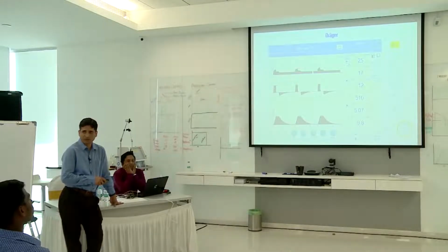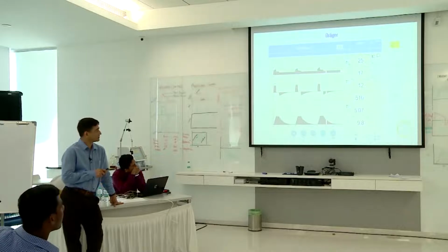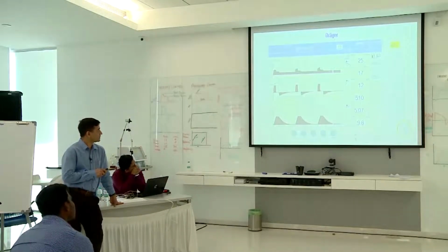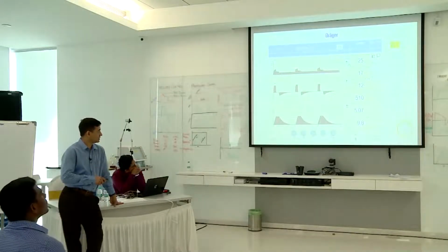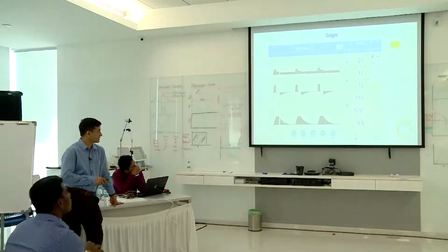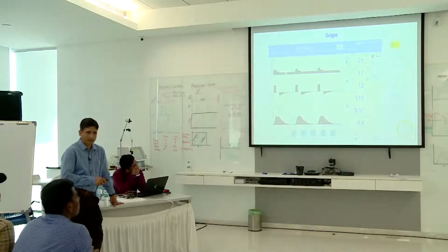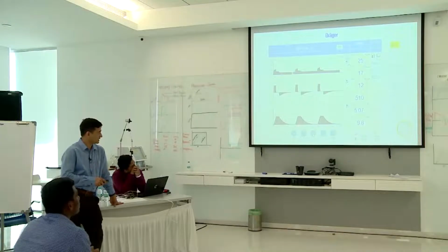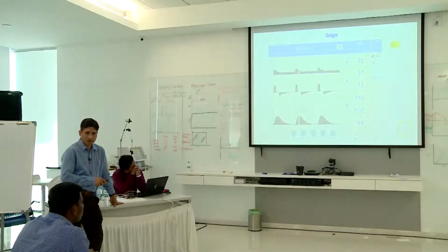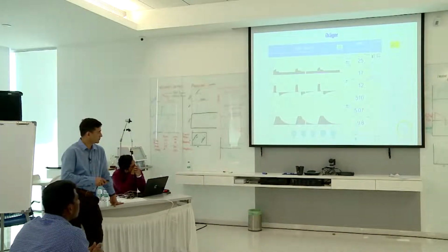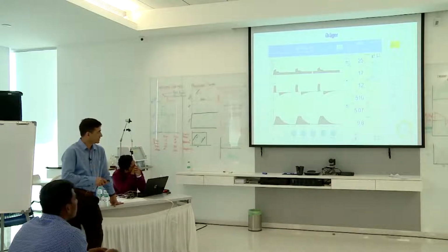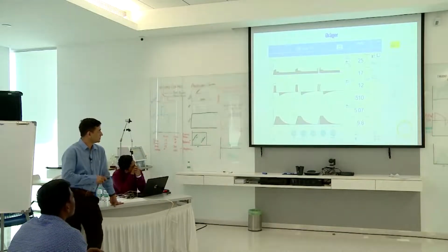If you put the patient on volume control ventilation, you need to monitor which pressure? Peak pressure and plateau pressure. Okay, now you see what the settings are. You can set the FiO2, you can set the tidal volume, you can have the option of setting the inspiratory pause or inspiratory time, rate. Okay, then PEEP.